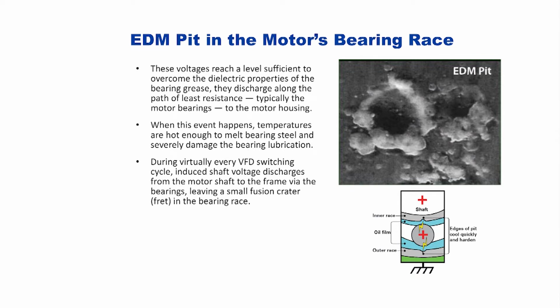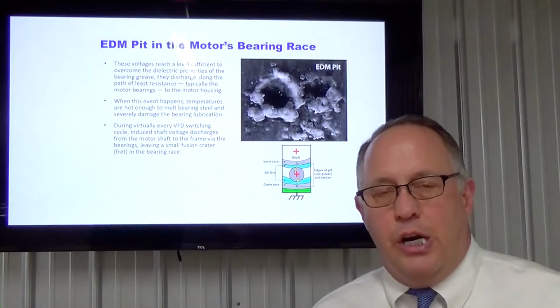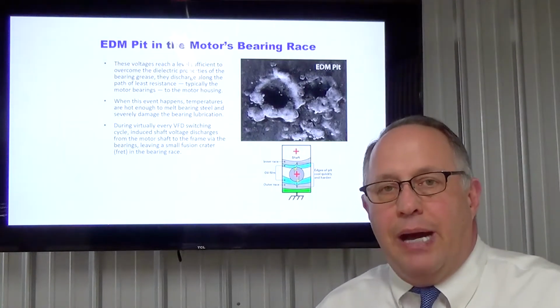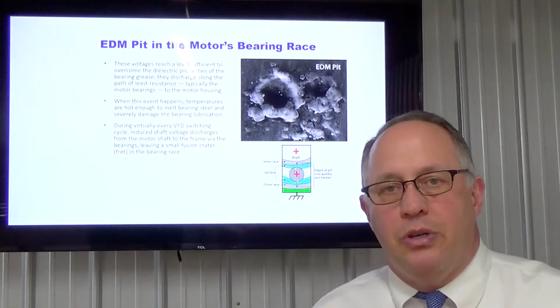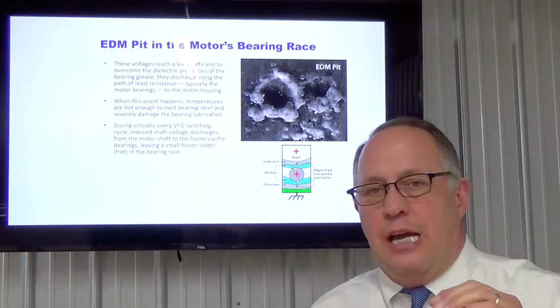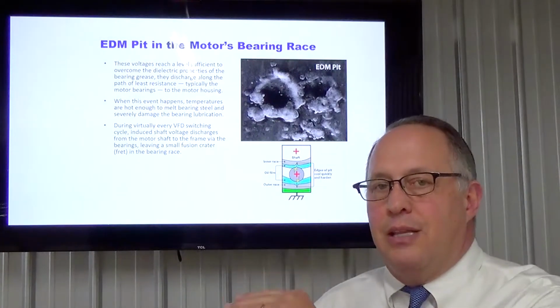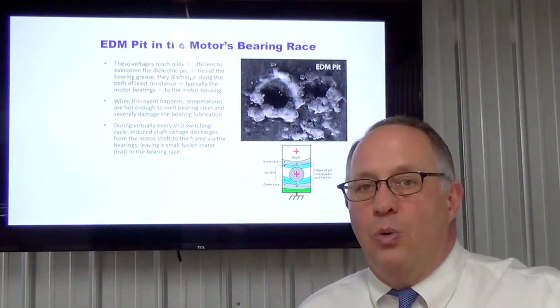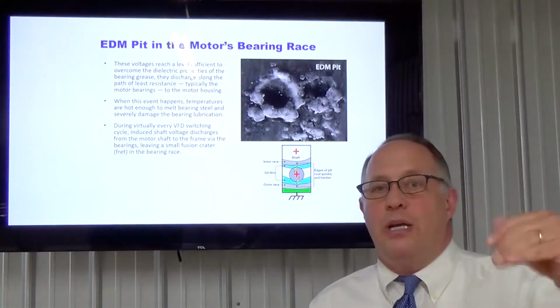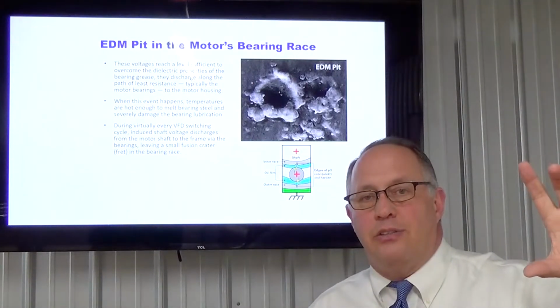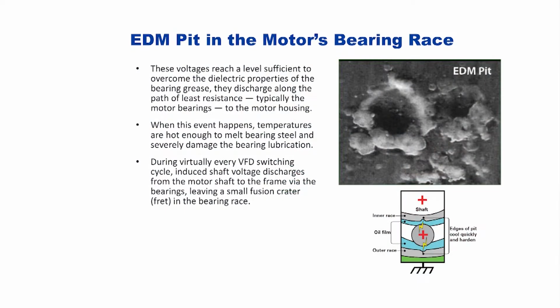These voltages reach a level sufficient to overcome the dielectric properties of the bearing grease. They discharge along the path of least resistance, typically the motor bearings, through to the motor housing. Grease as a dielectric is not very good. In fact, most common grease installed in bearings is only good for 0.4 volts of dielectric strength. In other words, any voltage on that shaft higher than 0.4 volts, and remember we said these voltages can get from 20 to 120 volts, so obviously over 0.4 volts, has gone over the dielectric strength of the grease itself, and an arc can flow across that. When that happens, temperatures are extremely hot, hot enough to melt bearing steel and severely damage bearing lubrication. In other words, burn the grease and pit into the race.